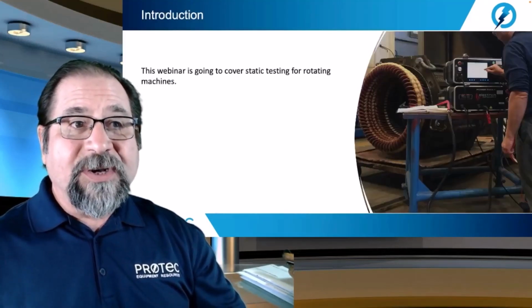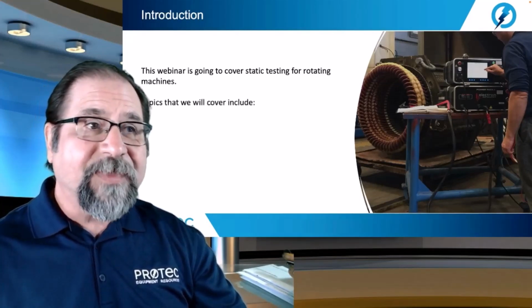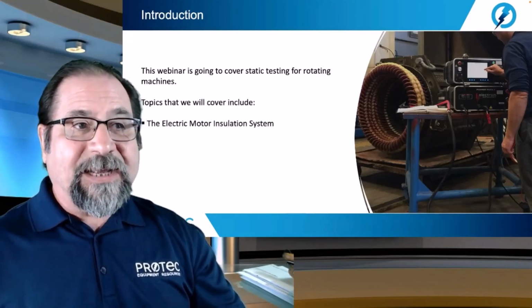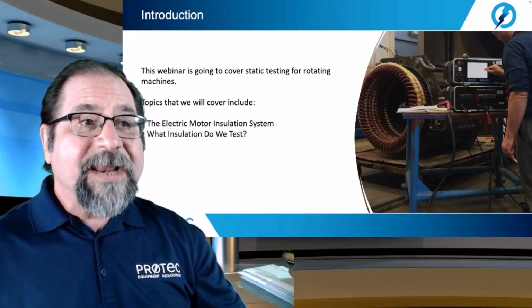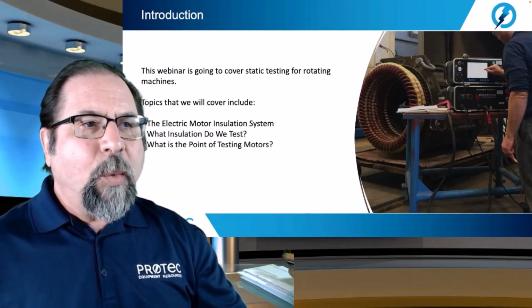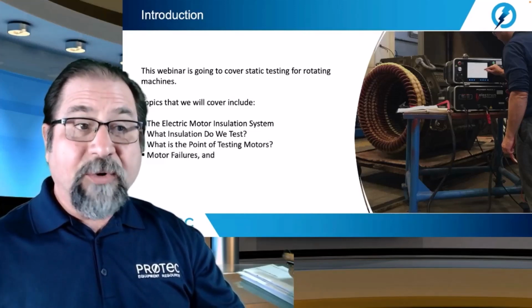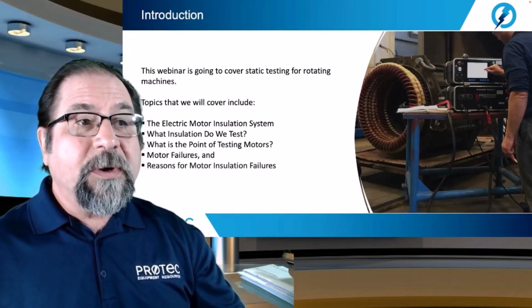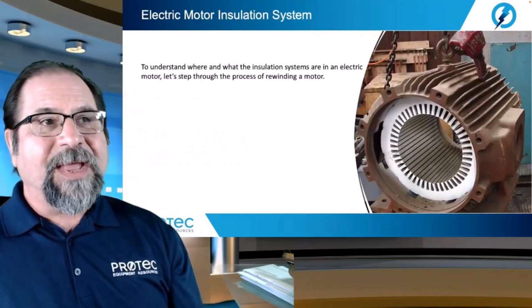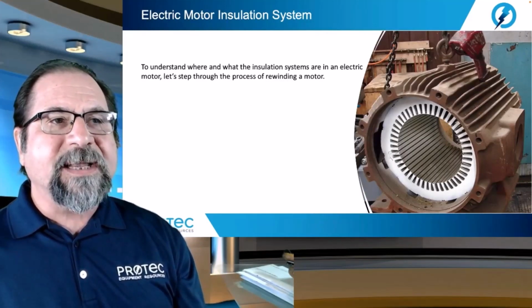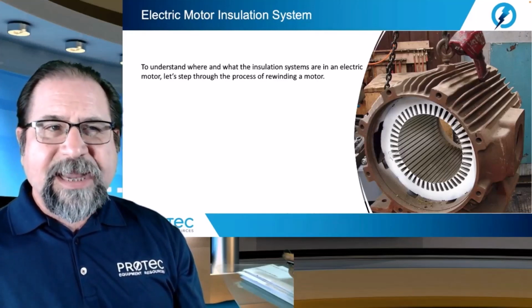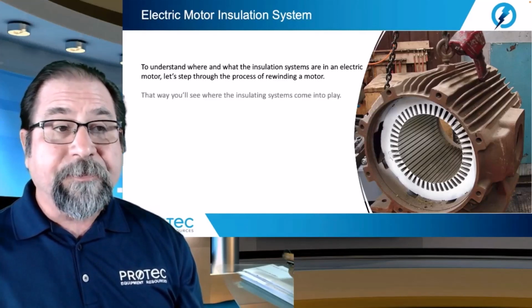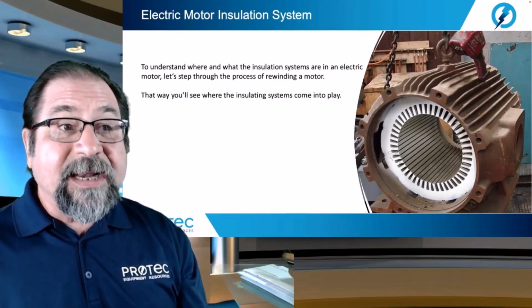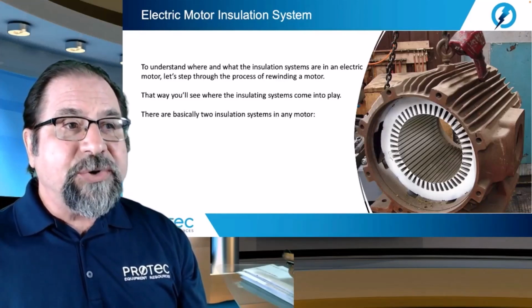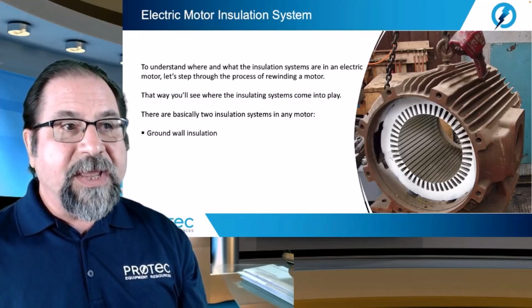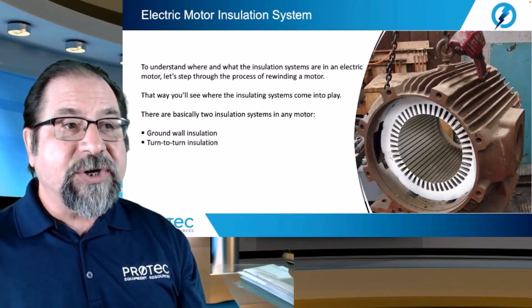This webinar is going to cover static testing for rotating machines. The topics that we're going to include: the electrical motor insulating system. What insulation do we actually test? What is the point of testing motors? Motor failures and reasons for motor insulation failures. All right, to understand where and what the insulation systems are in an electric motor, let's step through the process of rewinding a motor. That way you can see where the insulating systems come into play. There are basically two insulation systems in any motor: the ground wall insulation and the turn-to-turn insulation.